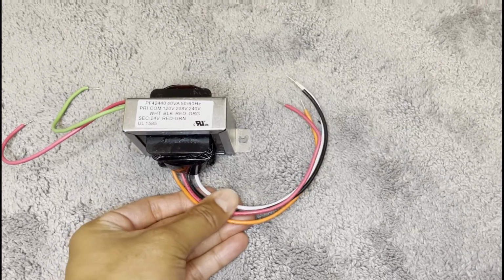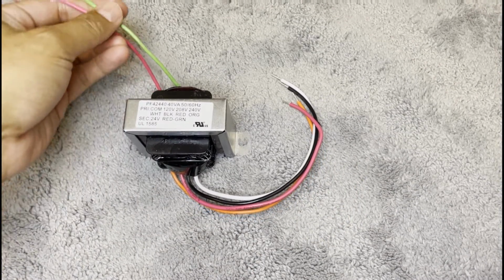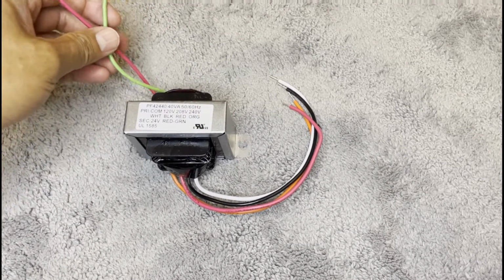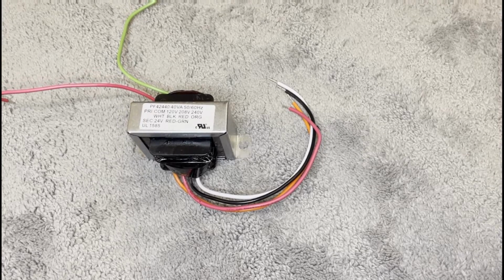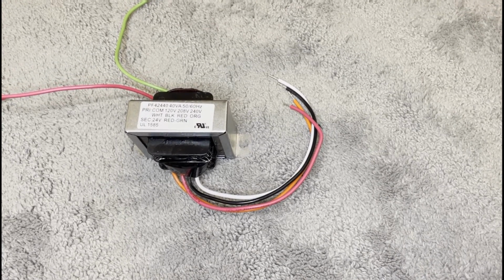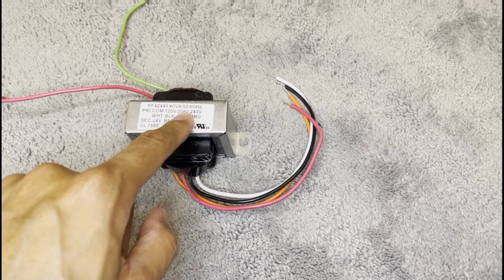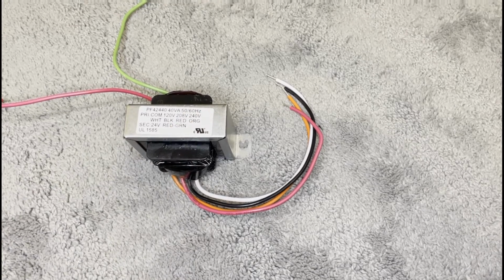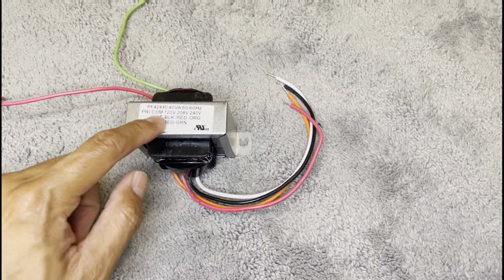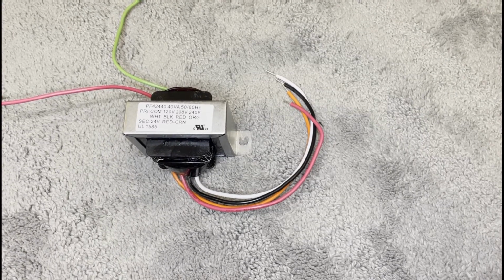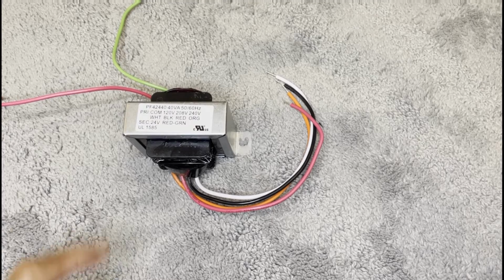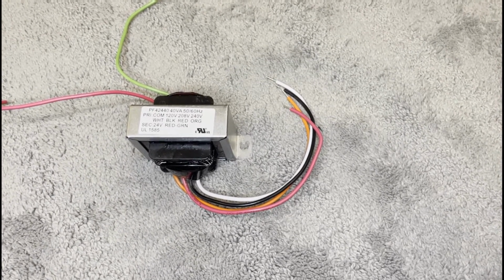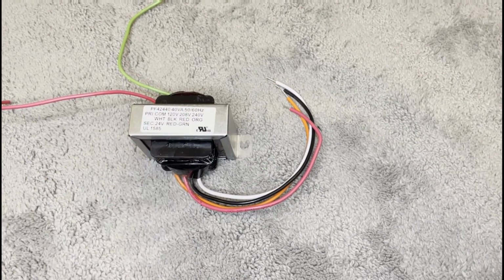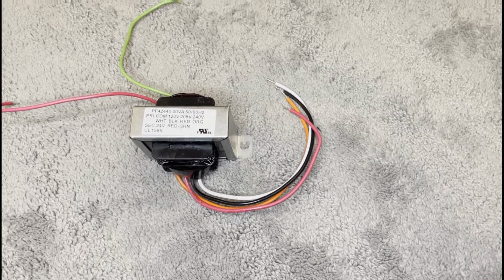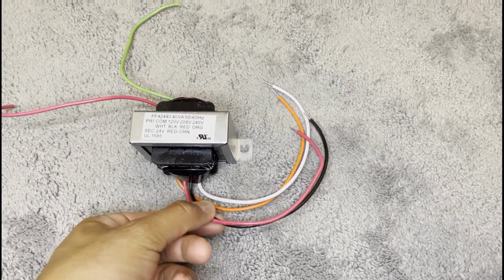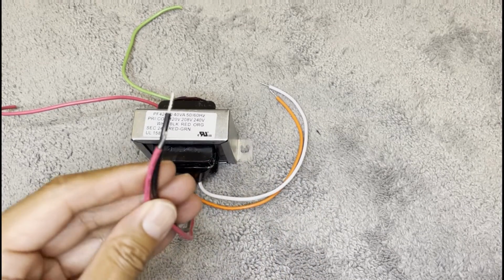These will be for your high voltage connection, and then the red and green on the other side, these are your low voltage wire connection. So this transformer, you can actually use this for 120 volt, 208 volt, and then 240 volts. If you're going to use 120, you will need white and black. And then for 208 volts, you would need white and red. And then for the 240 volts, in our case, we're going to be using white and orange. And then the red and black, since we're not going to use these, we're just going to cap them.